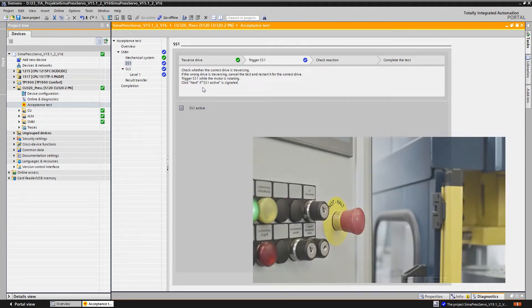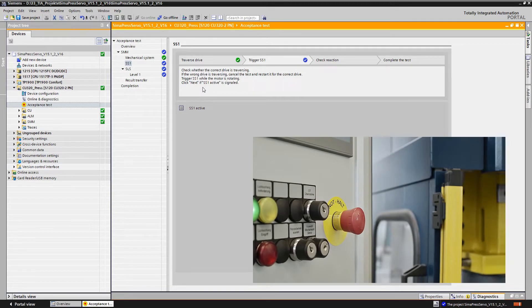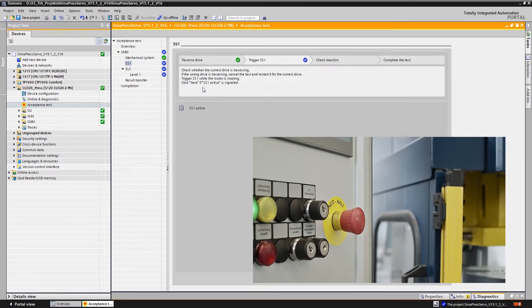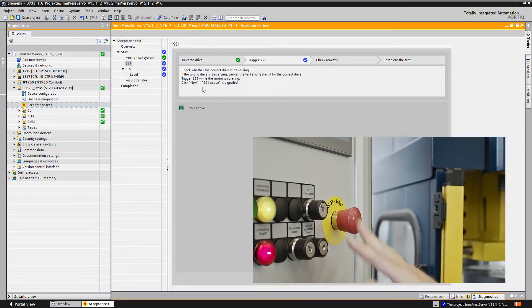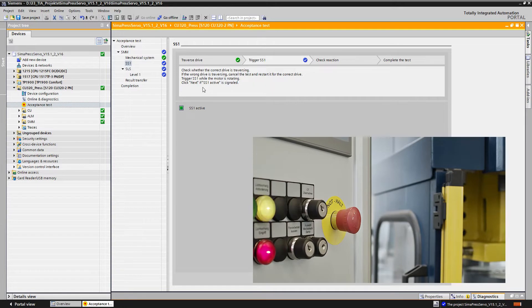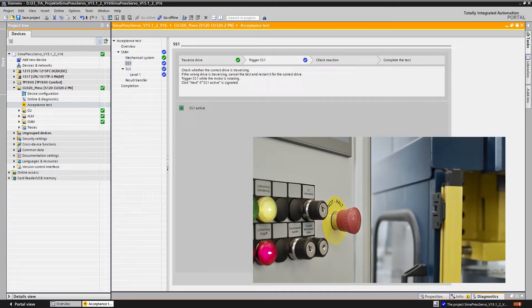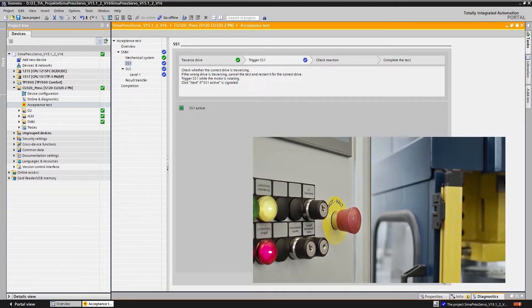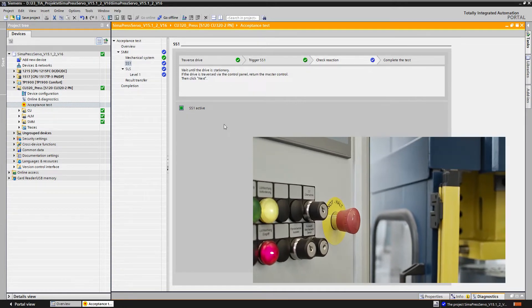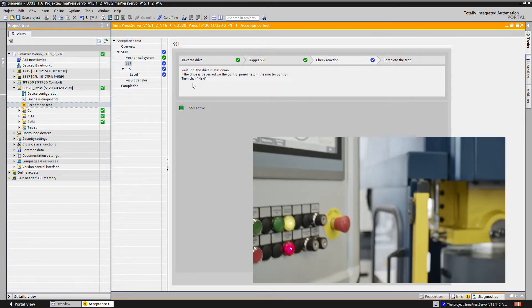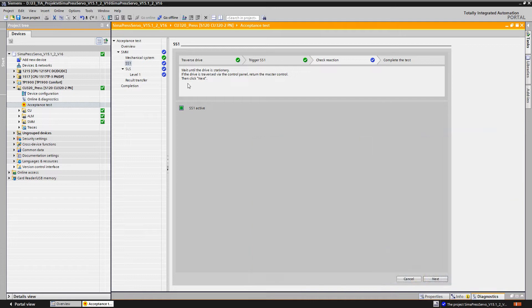We now test whether the correct drive moves, that's the press ram. Then we actuate the emergency stop command device using it to select the safety function SS1 and then wait until the drive stops.